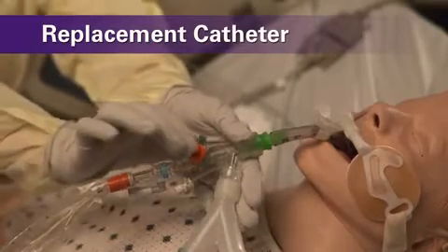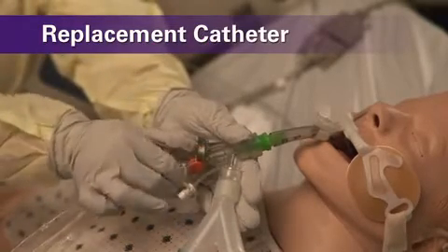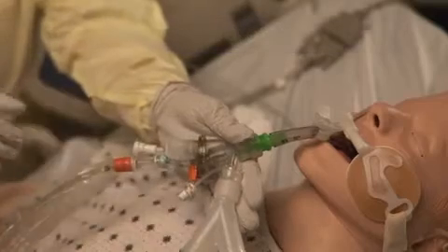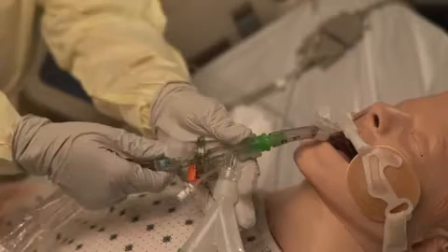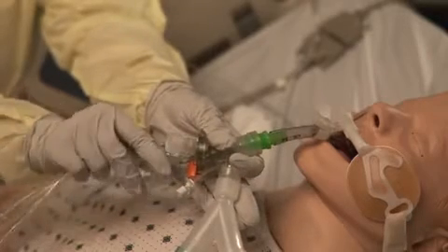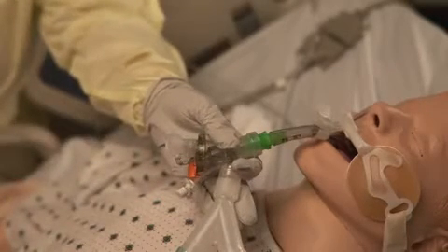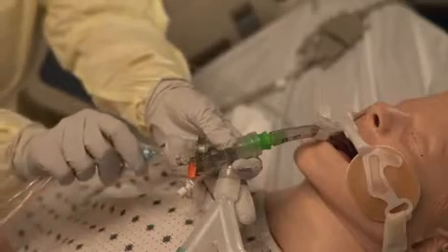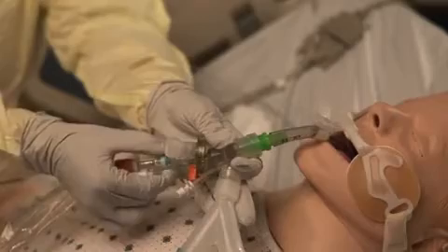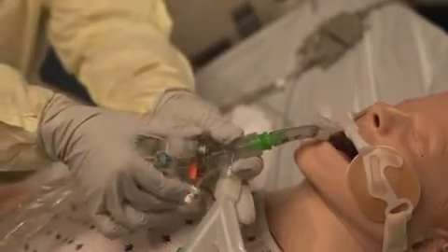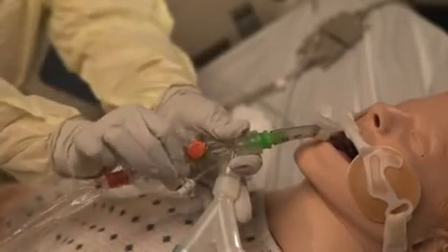Stabilize the artificial airway with one hand. Ensure the Kimvent MAP closed suction manifold is rotated to the alternate therapy or off position with seal cassette. Detach by rotating the replacement catheter counterclockwise. Replace with a new replacement catheter by inserting the catheter and rotating clockwise until a snug fit is reached. Then return the catheter back to the desired position.